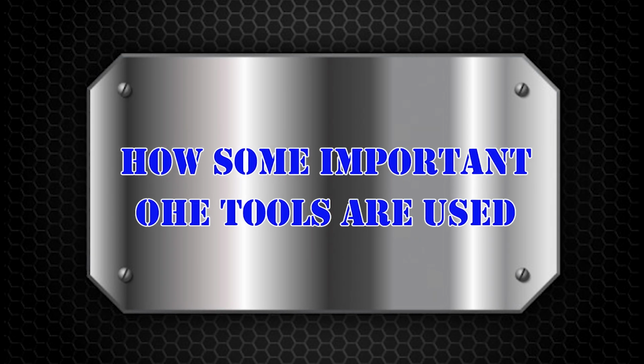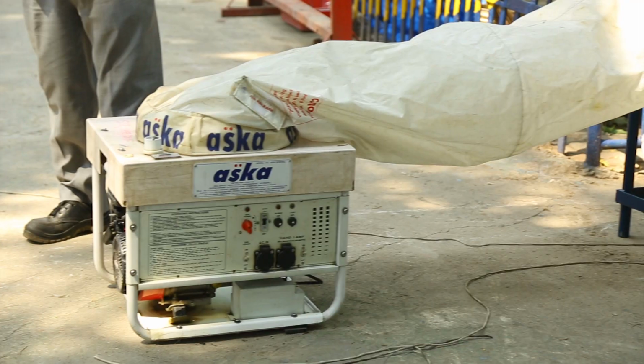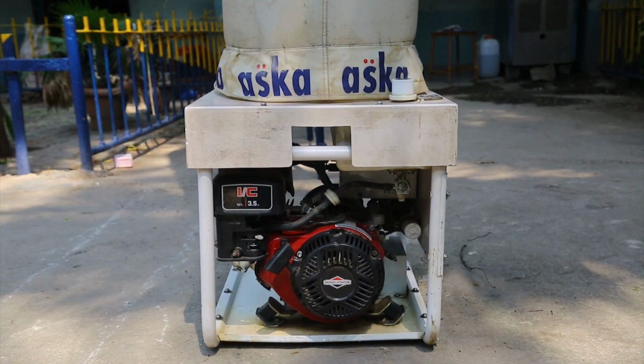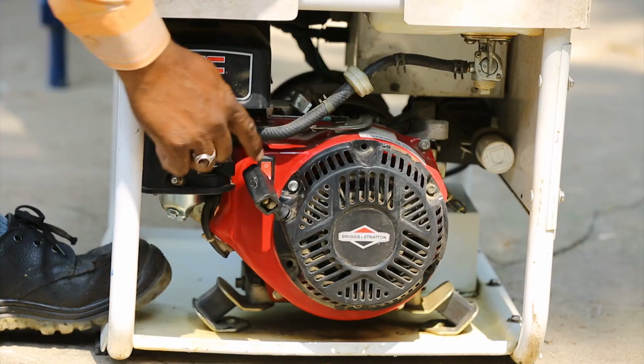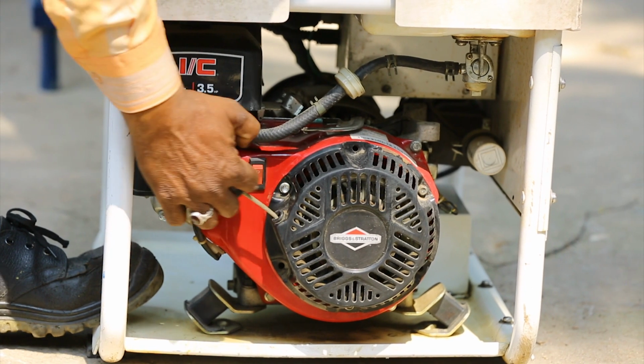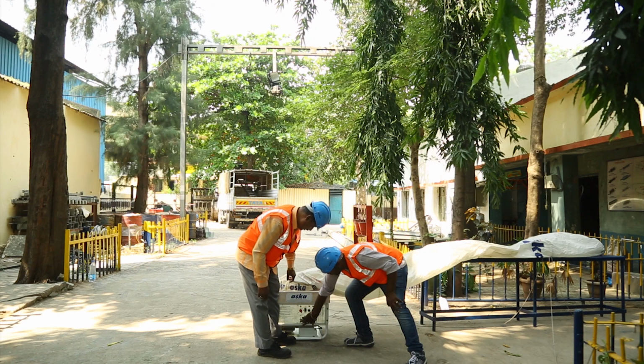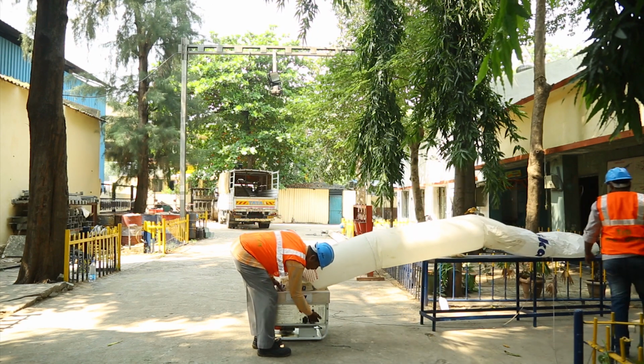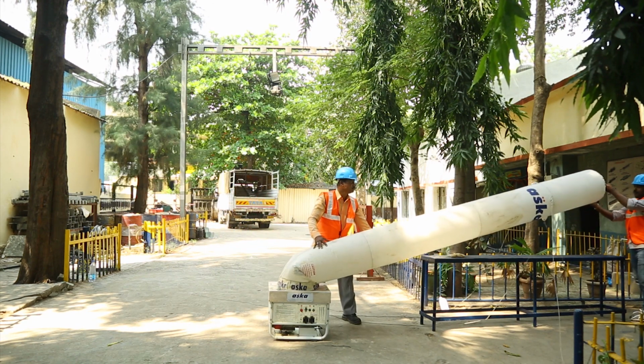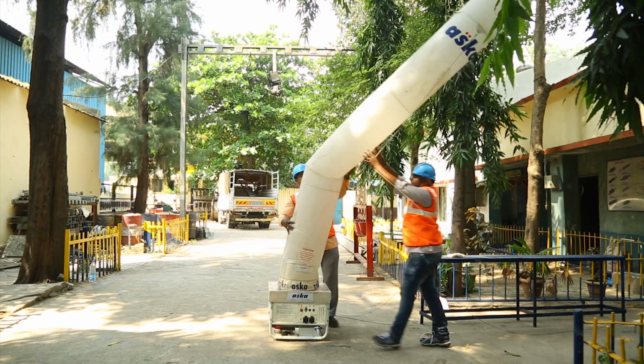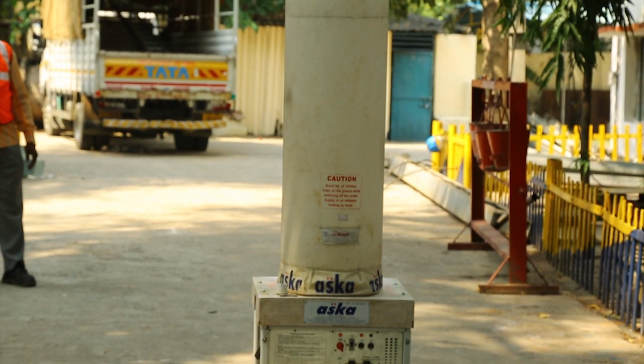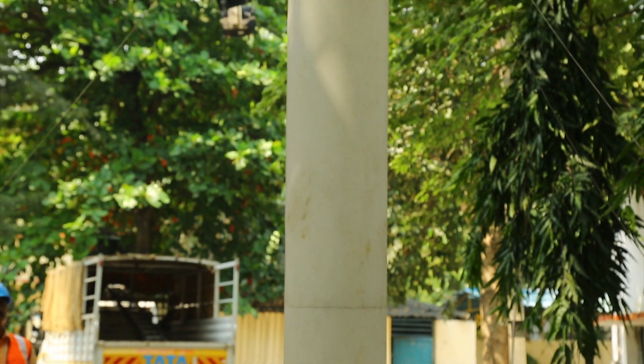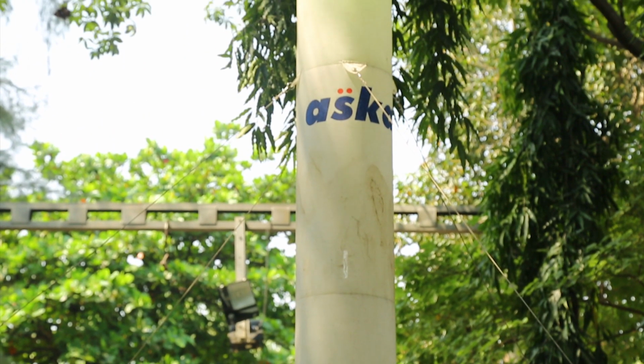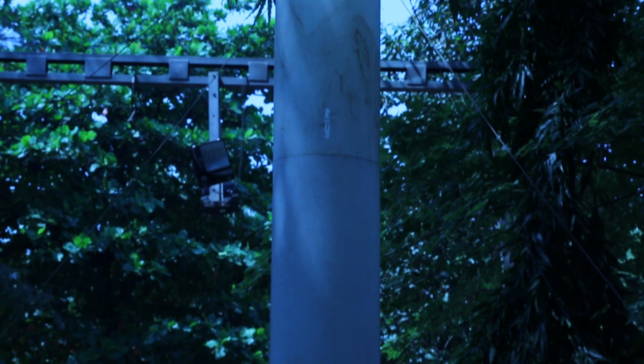How some important OHE tools are used. ASKA lamps. These are portable, inflatable emergency lighting system used in OHE breakdowns when daylight is insufficient. The system consists of inbuilt genset of 1.2 kVA, 2 blowers, 400-watt metal halide lamp. First, the user has to switch on the genset and then blowers to inflate the cloth at a height of 4.5 meters from the ground level. Further, we switch on the lamp which illuminates an area.